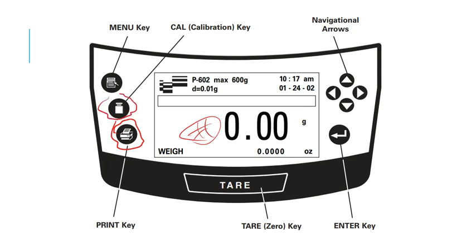Here I see something like an icon of a calibration weight, and if it's not that icon, they might just list CAL for calibration. That is where we would go to do the external or the internal calibrations. We have the balance go into those respective modes. So once I press the cal button, it will say, what do you want to do, internal or external, most of the time. And then I can have my choice of which one I would like the balance to perform. If I want to do an external one, then I need to make sure that those calibration weights are ready to go. Next up is the menu up here in the top left-hand corner.